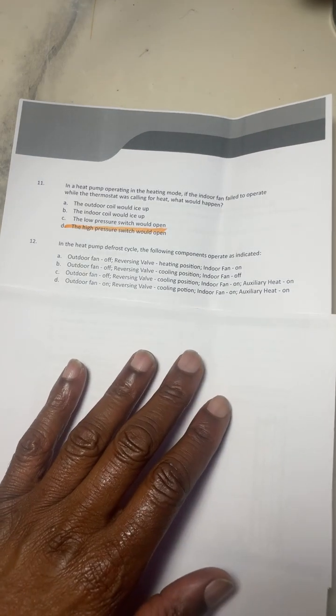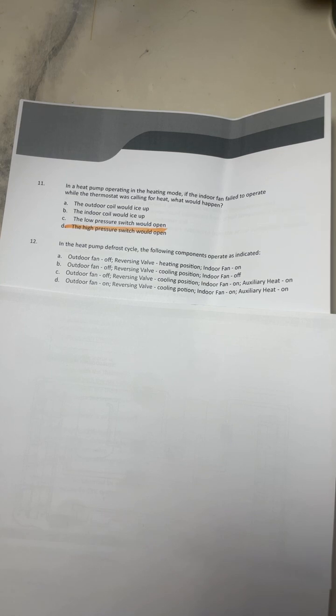Number 12. In the heat pump defrost cycle, the following components operating is indicated. A, outdoor fan is off, reversing valve heating position, indoor fan on. Or B, outdoor fan off, reversing valve in cooling position, indoor fan off. C, the outdoor fan off, reversing valve cooling position, indoor fan on, auxiliary heat on. Or D, outdoor fan on, reversing valve in cooling position, indoor fan on, auxiliary heat on. Answer is C.